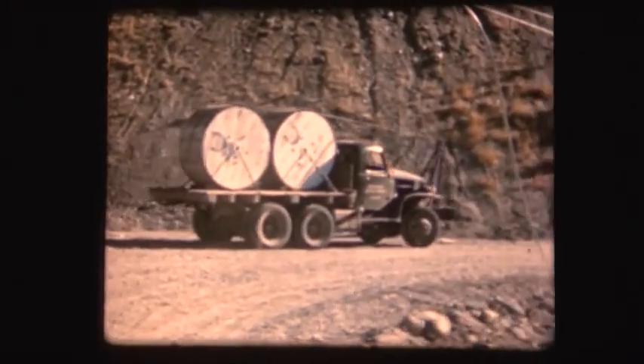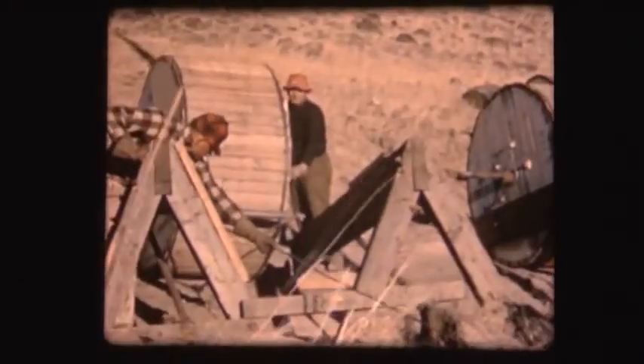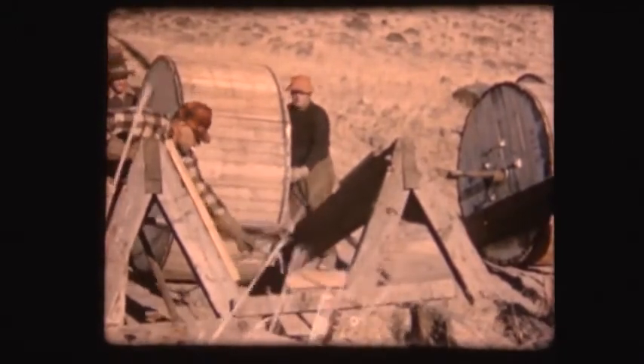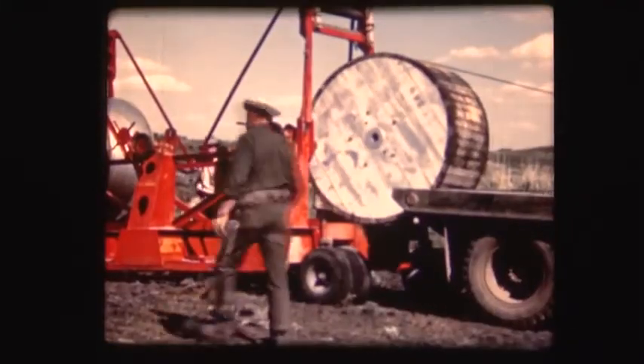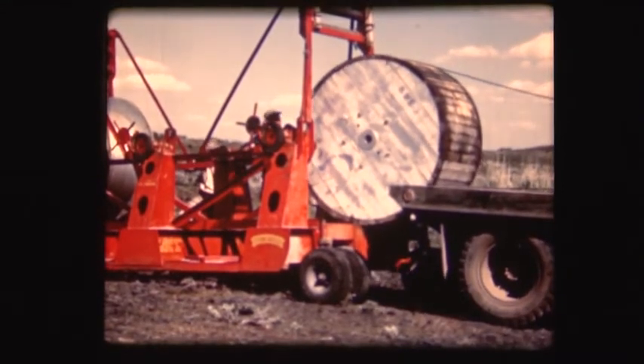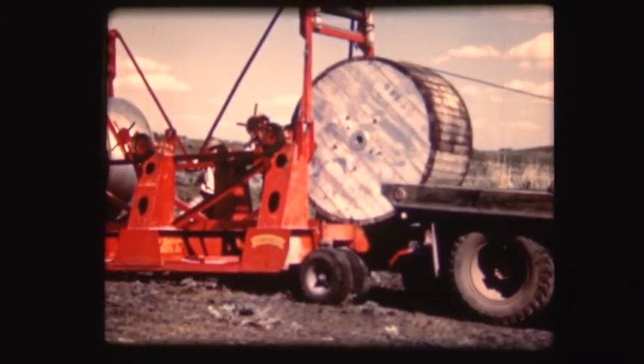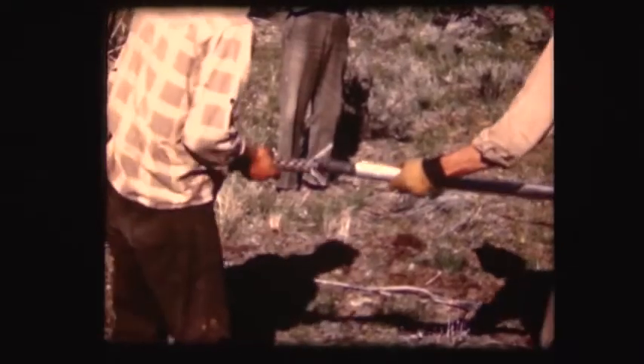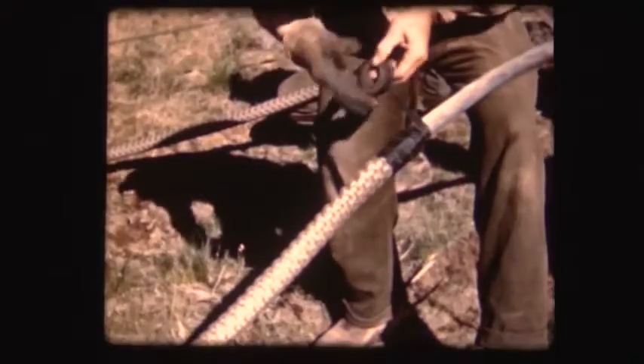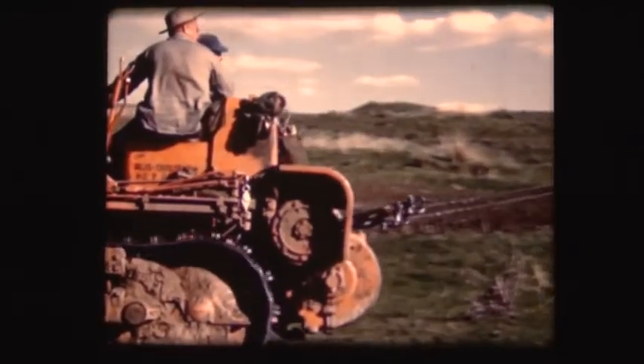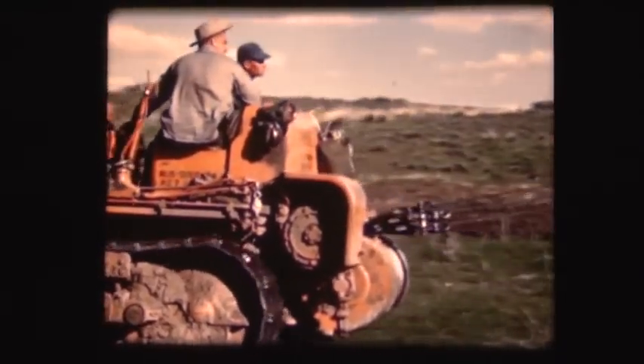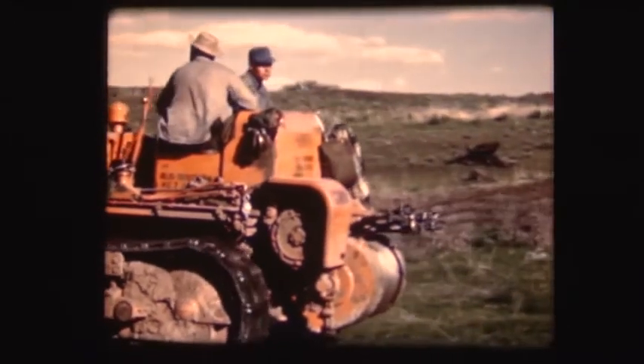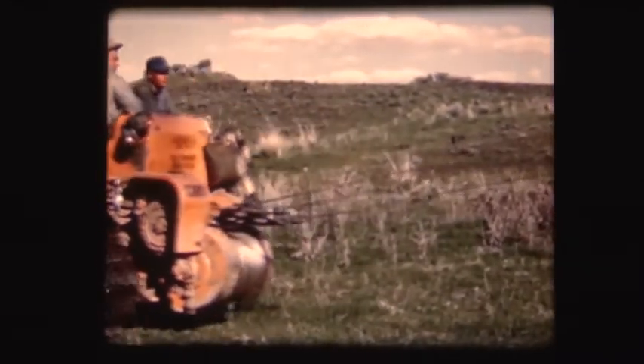Reels are hauled to the designated spots for unloading. They may be placed on simple wood horses, or preferably on more elaborate trailer-mounted reel jacks with braking devices. In either case, the reels are opened and wire mesh fasteners known as stringing socks are used to attach the ends of the conductor to steel cables called sock lines. In a typical situation, a crawler tractor is used, unreeling three, or in some cases, as many as six or seven conductors at once.